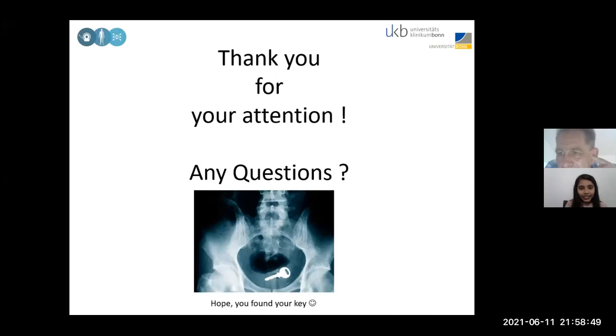What remedial action can be taken if a medical facility has not performed any commissioning and acceptance testing on equipment? Shall we depend on the constancy tests made by other physicists or biomedical engineers? It's a good question. If he's inexperienced and really feels not very secure doing commissioning, I would recommend, if there's a possibility, getting an experienced person, maybe from another clinic, involved. If he has to do it himself, then he has to work very closely with the vendor. The vendor usually has experience in setting up the machine, because it's not the first one they sell.